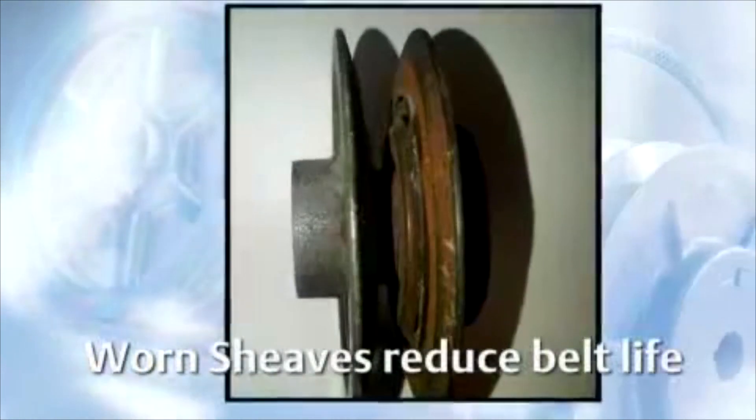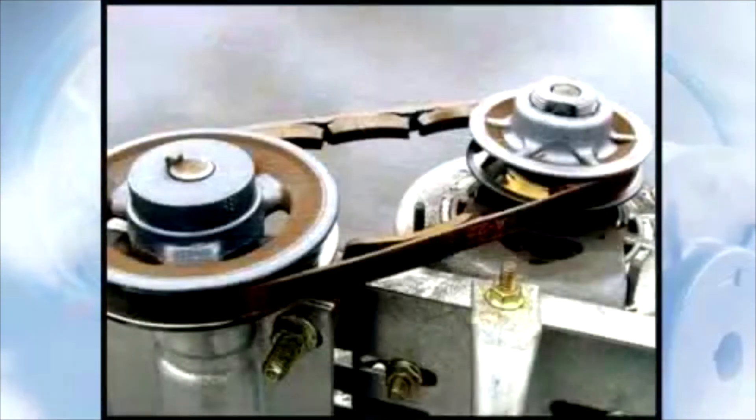Worn, damaged, or dirty sheaves will substantially reduce belt life. Nicks or gouges can cut the belt. Dirt and debris in the grooves can abrade the belt. Oil can attack the belt materials, and worn grooves may allow the belt to bottom out, slip, and become damaged.